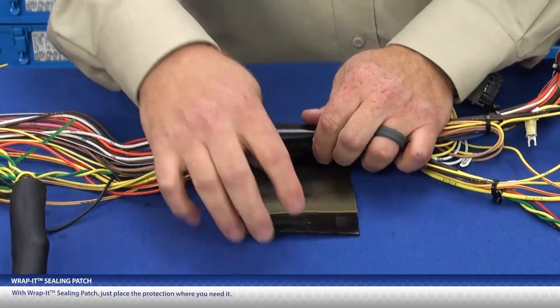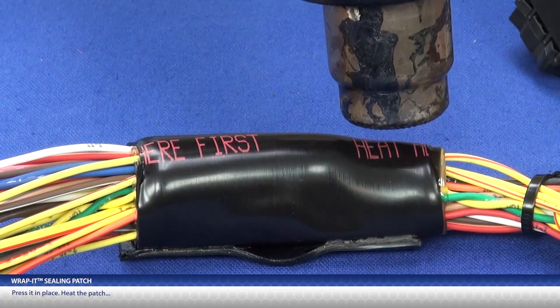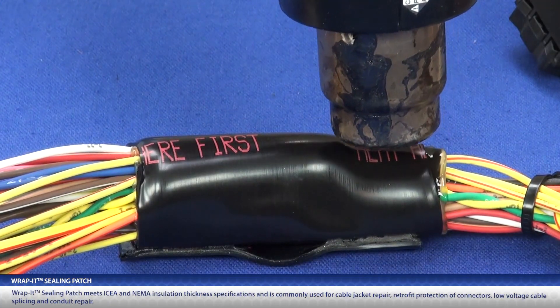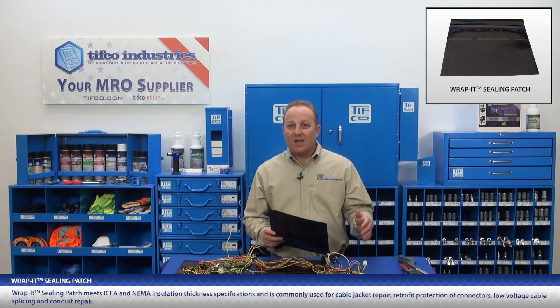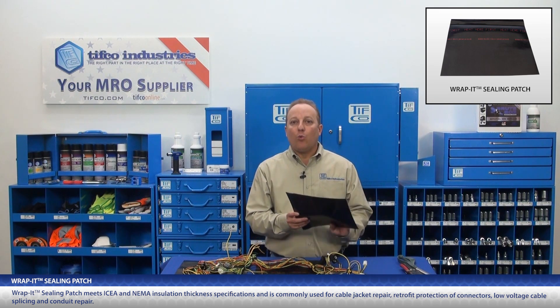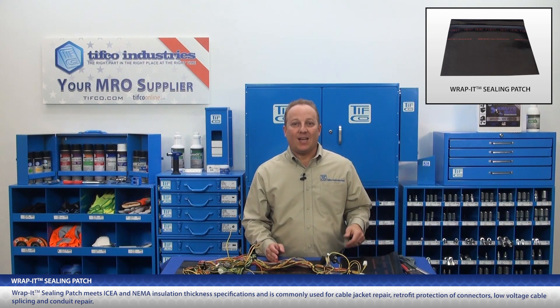With Wrap-It Sealing Patch, just place the protection where you need it, press it in place, heat the patch, and you're sealed. Wrap-It Sealing Patch meets ICEA and NEMA insulation thickness specifications and is commonly used for cable jacket repair, retrofit protection of connectors, low voltage cable splicing, and conduit repair.